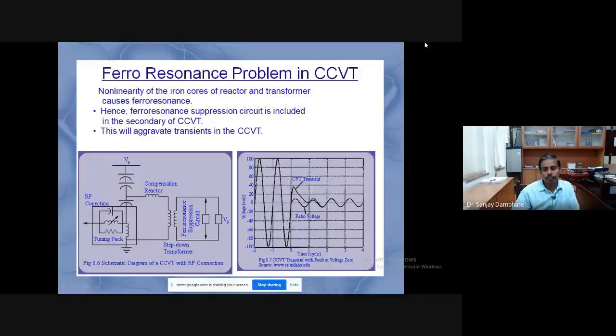Coming to the CCVT, that is capacitive coupled voltage transformer. The point is that we need to reduce the system voltage, which is very high, so you can comfortably use a transformer. But reducing 440 kV to 5 or 10 volts directly would make the transformer cost very high, and that's why a capacitor divider circuit is used, and that is the CCVT.